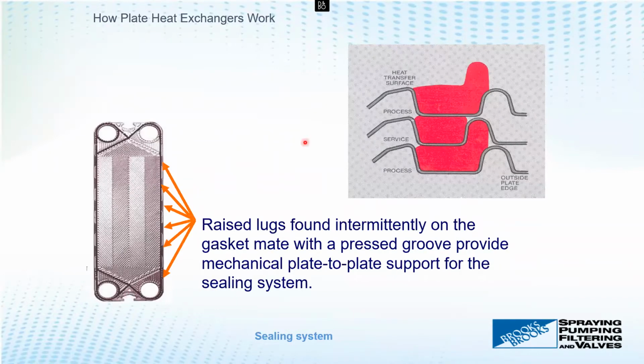If we look at a cross section, this is the face of the plates, and now we have a bunch of plates stacked to make a plate pack. We have cold fluid through here, hot fluid through here, cold fluid through here. This is the flow side of the plates, and this is the outside to atmosphere. That's the gasket groove I talked about, that we either push spools into, or in the old days you'd glue along the bottom of each plate and put the gasket in. In this case, we press them in or clip them in.